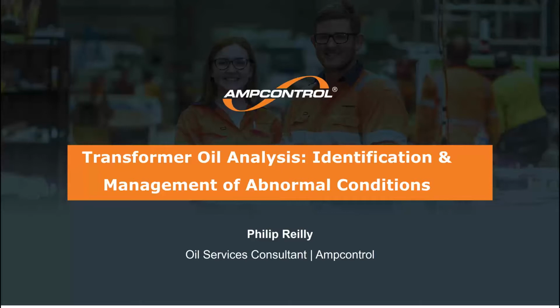And reliability surveys based on standardized questionnaires developed by CIGRE show failure rates are less than 1% for substation type transformers at voltages even greater than 300 kV, with generator step-up transformer failure rates reported to be slightly higher. And some experts in the industry believe rates of failure do increase as an asset ages.